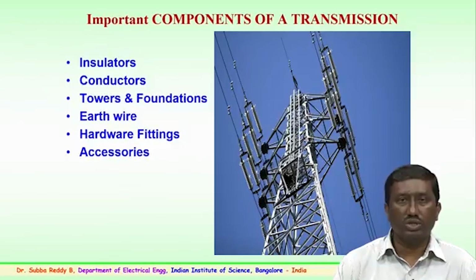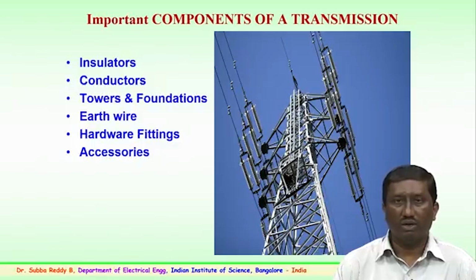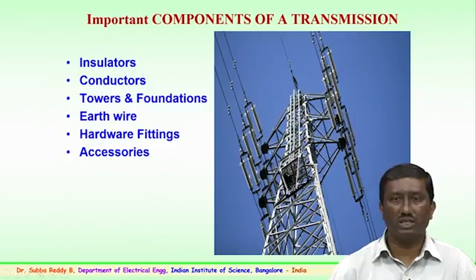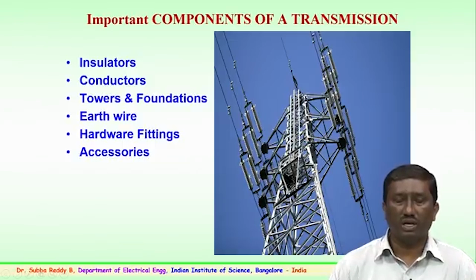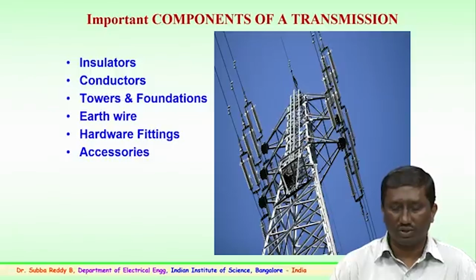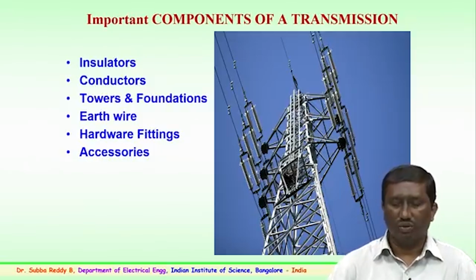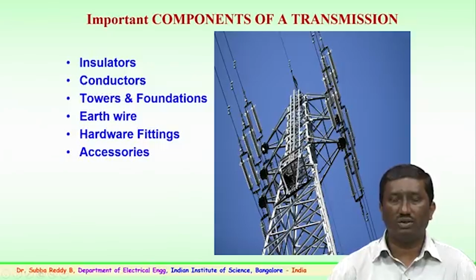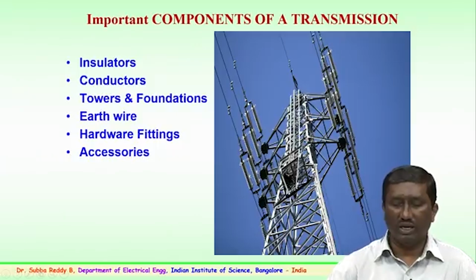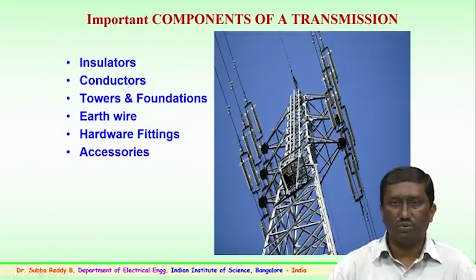This shows the most important components of a transmission network, the transmission system. An example is shown here, a transmission tower, where the tower consists of the following components which are very important. The first is the insulator. As you can see here, there are various types of insulators which are being used for transmission. The insulators are arranged in different configurations, like the suspension, tension, quadruple tension, V suspension, and so on and so forth. So, what is the importance of this insulator? The insulator is an important component of a transmission system. It performs a dual function. One is it supports the conductor mechanically, and the other is it electrically isolates the conductor from the tower. So, this performs a dual function.